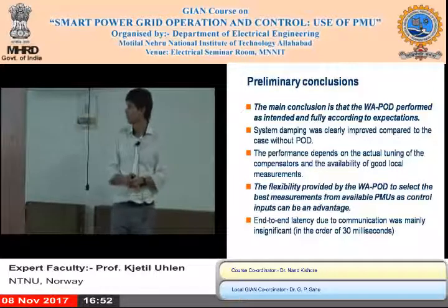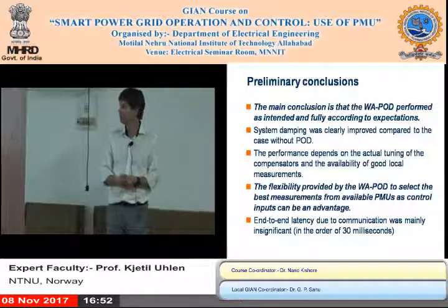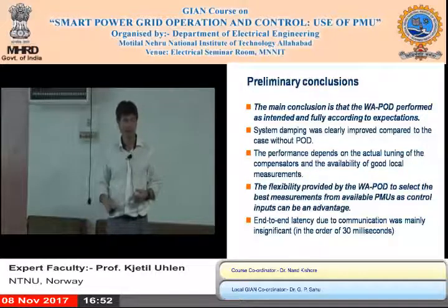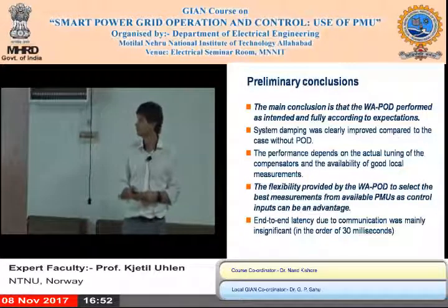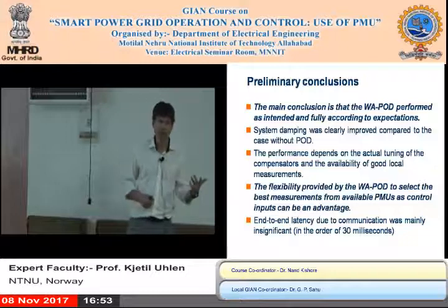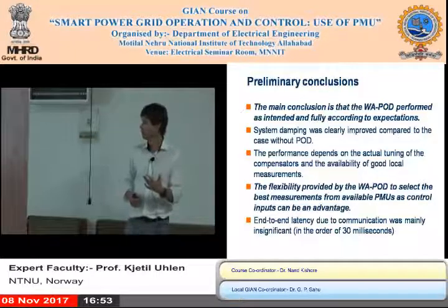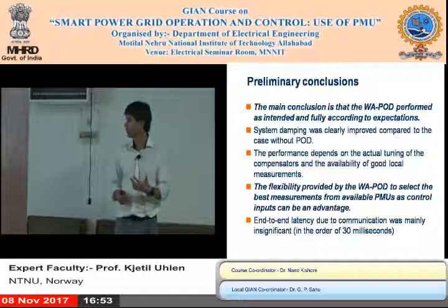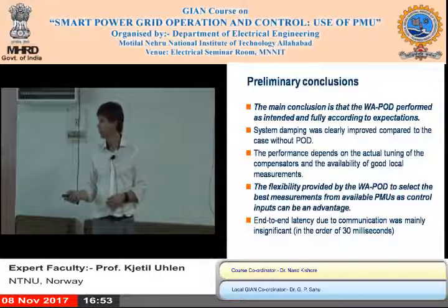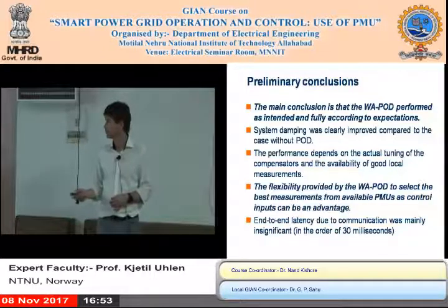that it performed as intended, and also fully according to our expectations based on the simulation results. And of course, in reality, it depends very much on how good your local measurements are. Depends on the actual tuning of the compensators and so on.